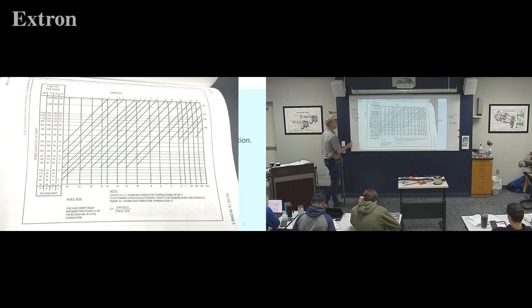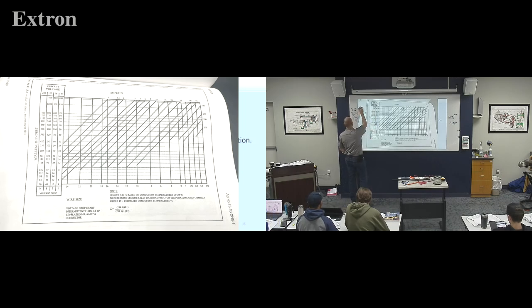We start off with 28 volts, in the top left. We say, okay, 40 foot, so we scroll down until we get to 40 foot. If I went all the way to the bottom, it would tell me my allowable voltage drop, just FYI — theoretically I might only end up with 26 or 27 volts at the component. But we'll go back up to where we should be: start with 28, check; down to 40 foot, check.